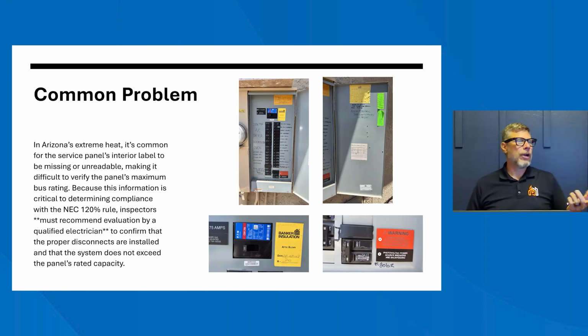Our disconnect on there is a 175 amp disconnect, and our solar array there was a 45 amp disconnect. Now, basic math that we just looked at, we know that that's probably underrated for the panel. So we probably could go a little bit larger, but we don't know. And the reason why we don't know is because we don't have a label.